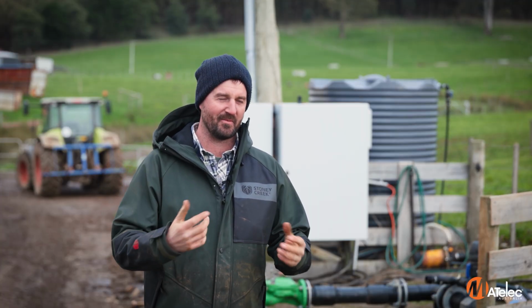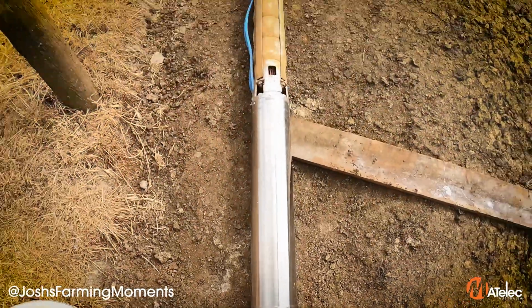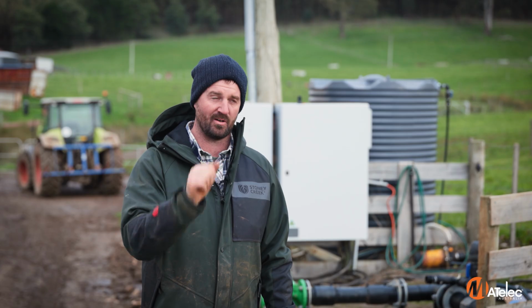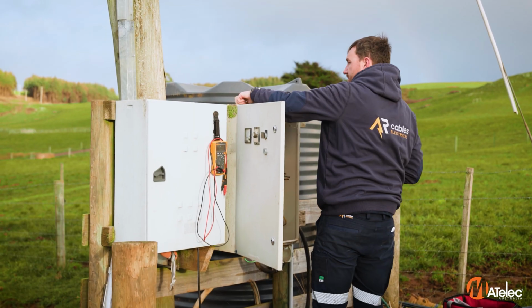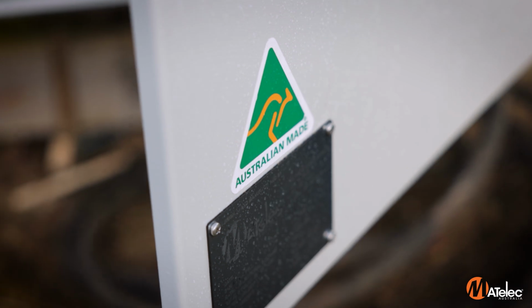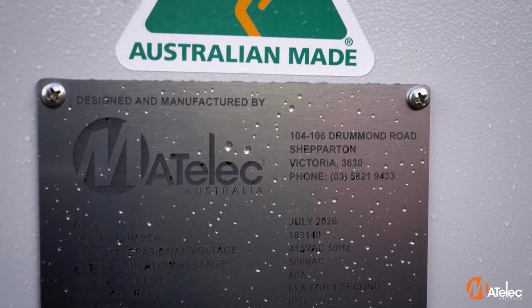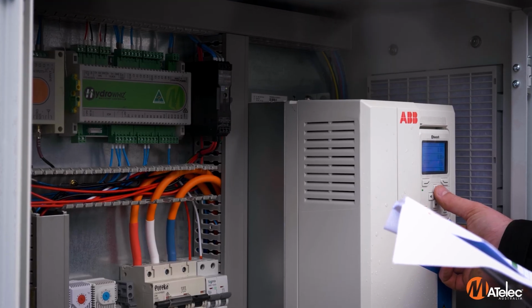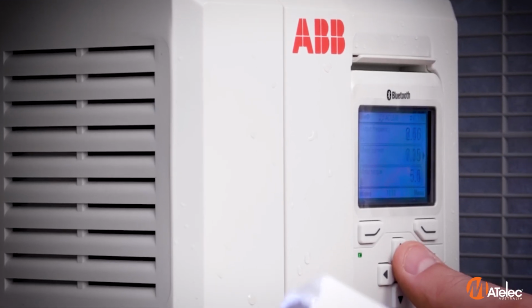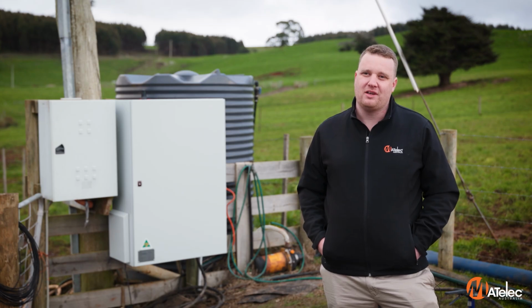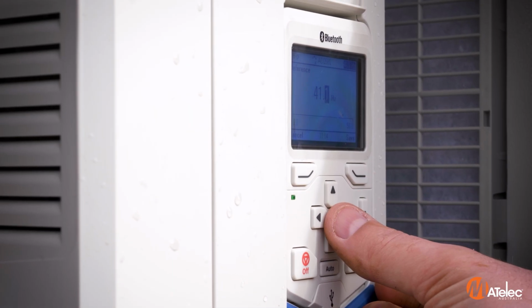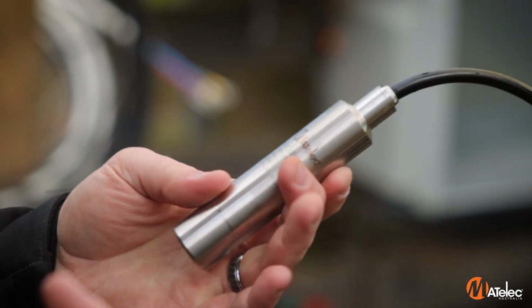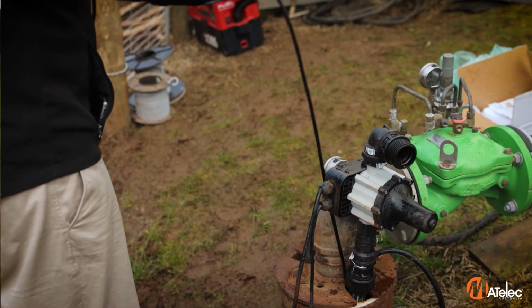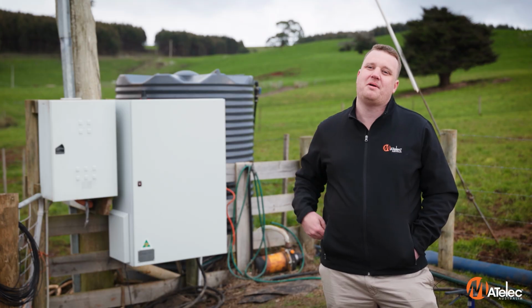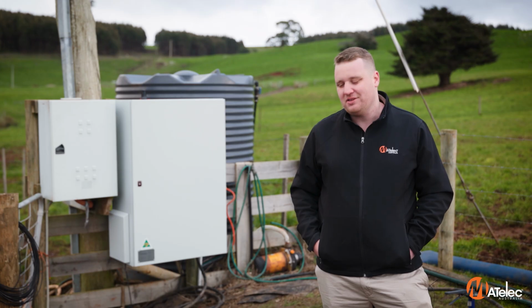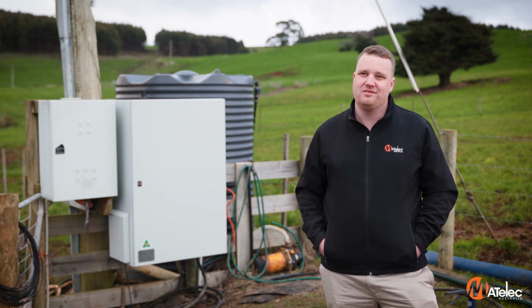So we've spent a lot of money on this pump, and we didn't have a fail-safe. And that was the biggest issue we had. We could only just turn on and off at that panel. And now with this new one, we've got a lot of fail-safes that will avoid any huge catastrophes like that. So now that we've gone to a VSD, the VSD has parameters around things like motor current and frequency. So it's monitoring if they go outside the set parameters, and that will give him some protection there. But we also have a level transducer in this bore now that's monitoring the level of the bore, and we use that to disable the pump as well. So he's got multiple levels of protection that's going to protect that asset that's down there, and has cost a lot of money.